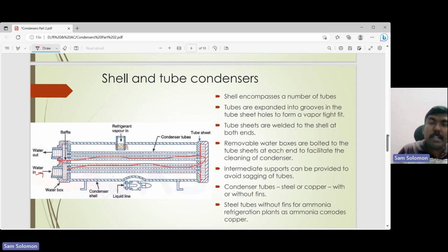So it passes the shell two times. So it's a two pass. It's a double pass, two shell pass condenser. Okay, so it is passing the shell two times. So it's a shell and tube condenser over here, and you can see that people normally use baffles in order to avoid the bending or sagging of tubes here, because they are very lengthy. In order to provide support, people use baffles, or you can have any type of intermediate support for that matter.